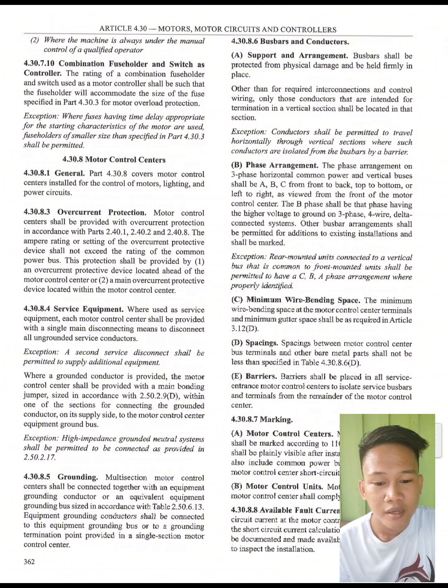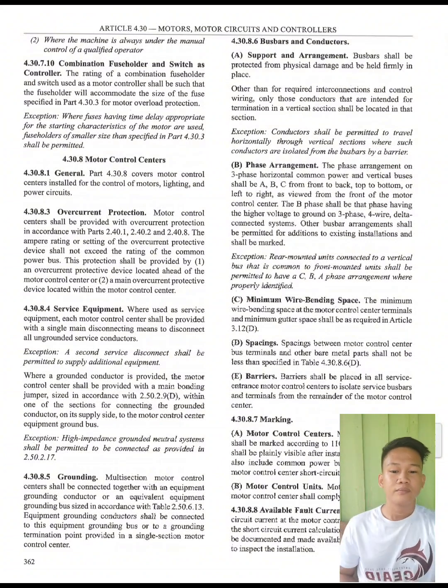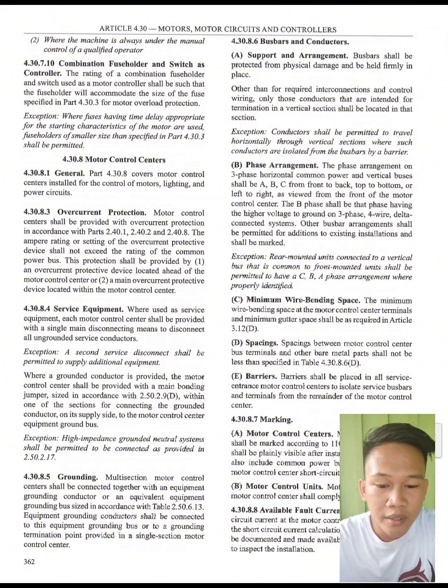So, we have here 4.30.8.5 Grounding. Multi-section motor control centers shall be connected together with an equipment grounding conductor or equivalent equipment grounding bus sized in accordance with Table 2.50.6.13. The equipment grounding conductor shall be connected to this equipment grounding bus or to a grounding termination point provided in a single-section motor control center.